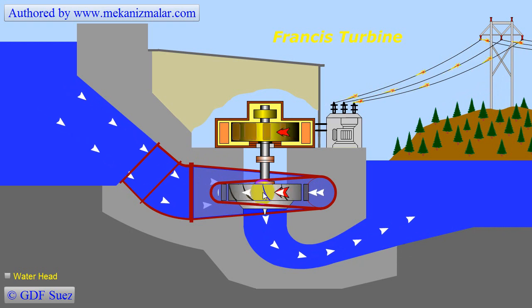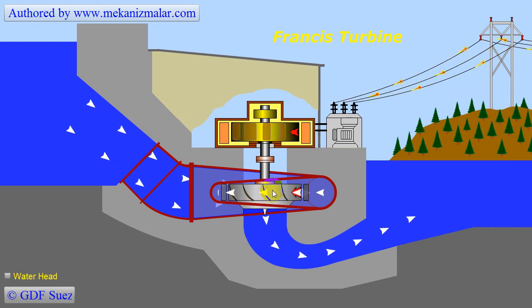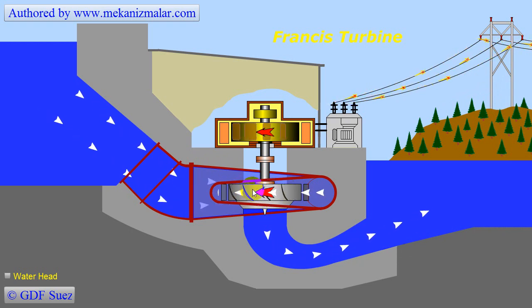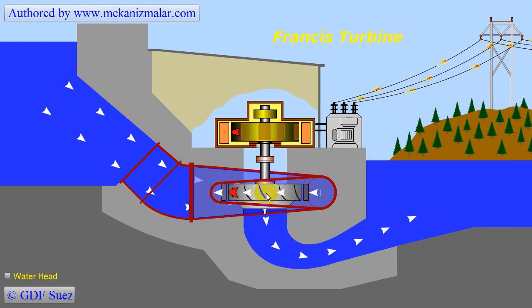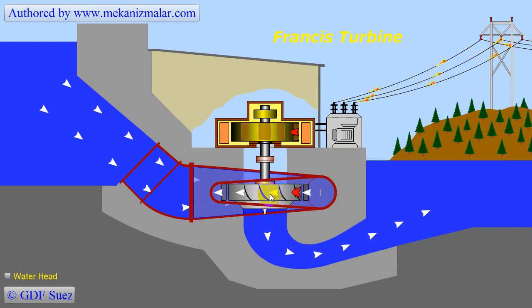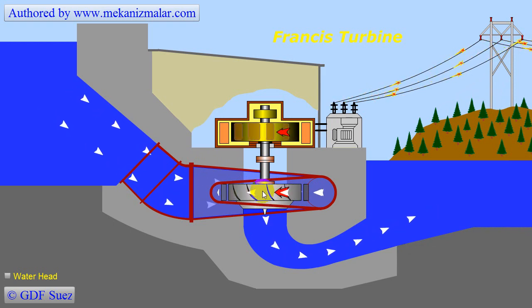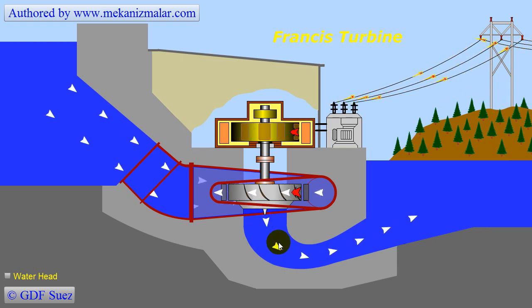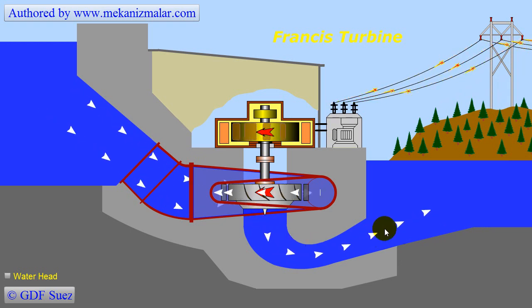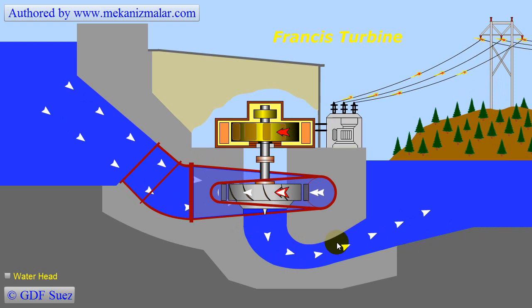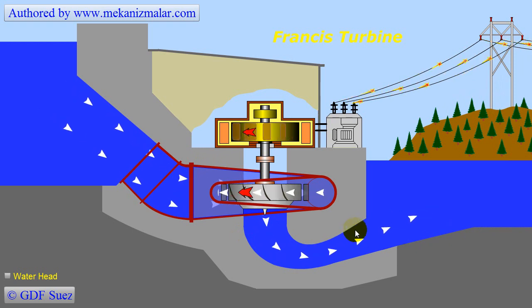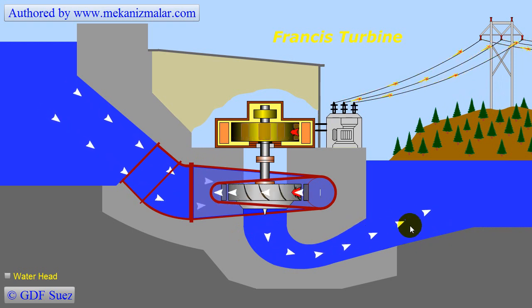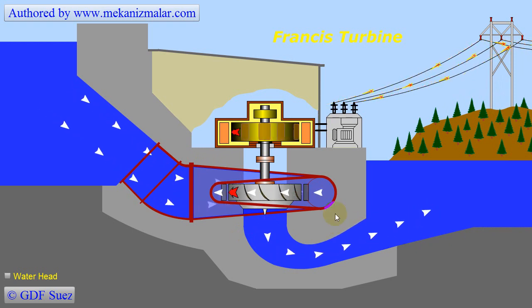The water pressure forces the runner to rotate. The rotation speed of the runner can be in the range of 80 to 1000 RPM. The water continues its motion downward under the runner to the exit pipe, which discharges the water to the environment as low-pressure water.